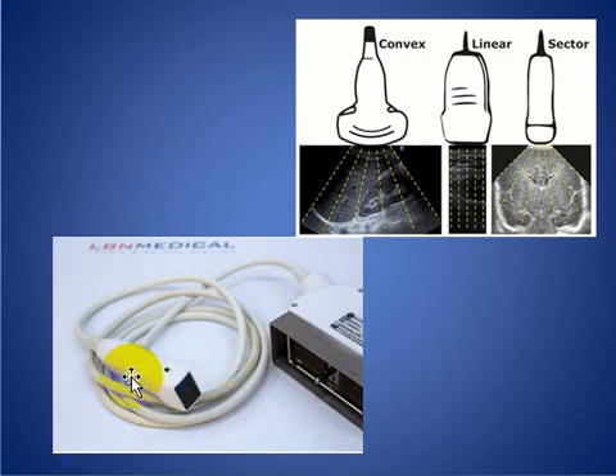The phased array transducer has a small footprint and low frequency, with a central frequency between 2 MHz and 7.5 MHz. The beam is narrow but expands depending on the applied frequency, and the near field resolution is poor.